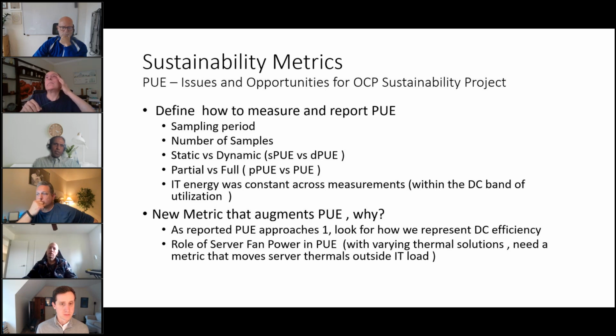The second thing vendors do is call everything PUE, but what they're actually reporting is a partial PUE. What I mean is, in a data center, they leave out the chillers, take only the power incoming into the data center hall, change some thermal equipment, and say, okay, here's my improved PUE, I can hit 1.07. Well, can you really? Because you didn't incorporate the chillers or their coefficient of performance - had you done that, maybe that number wouldn't be as rosy as presented.